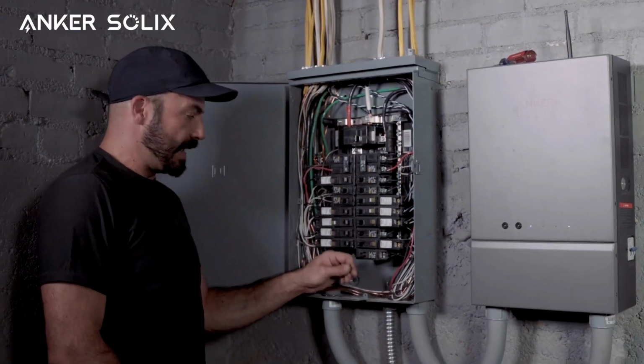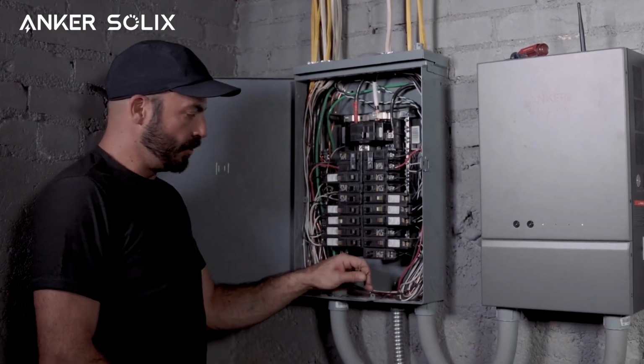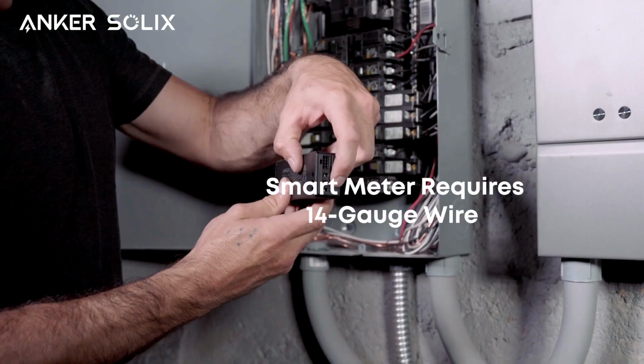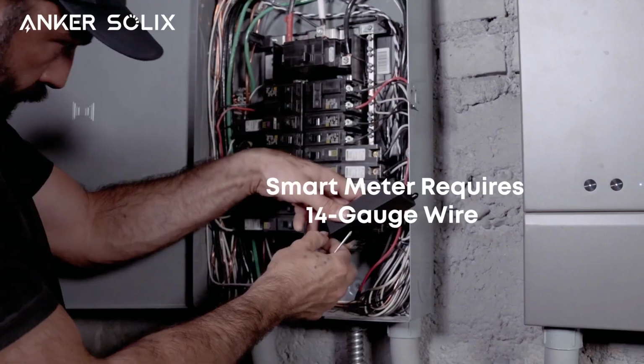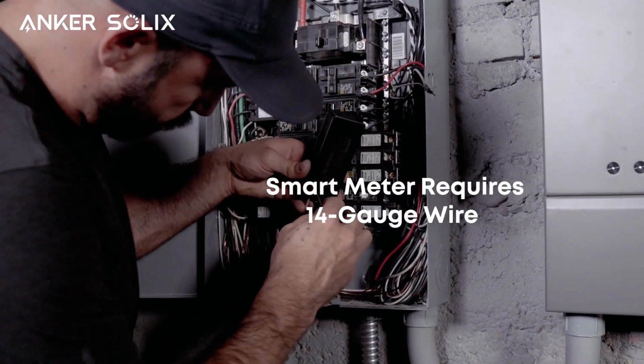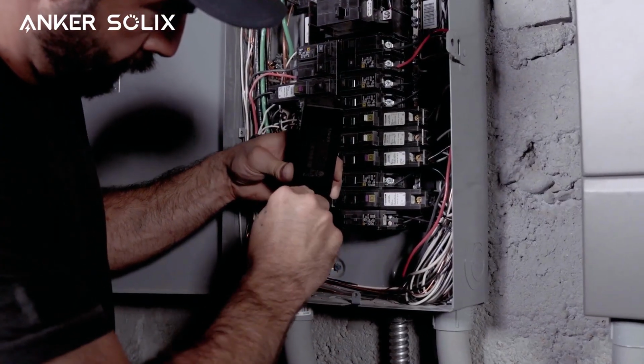Now that we have our neutral, L1, and L2 wires installed, make sure they are 14 gauge, because that's all that will fit in the ports of the smart meter. We can go ahead and install those and get them clamped down.